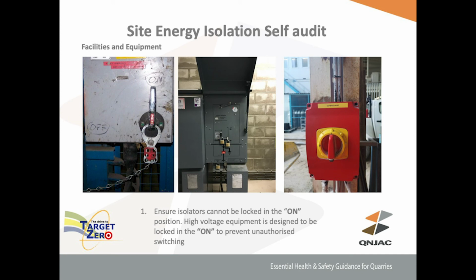You could actually lock them in the on and off position. That was an incident I investigated on a robot cell where two fitters had been working on a robot, isolating that device on and off several times during the day. On one occasion, they isolated it in the on position and went into the robot cell. Fortunately the robot didn't start up, but the manager went into the factory and saw it was isolated in the on position, and we got rid of all of those isolators as part of a company policy.